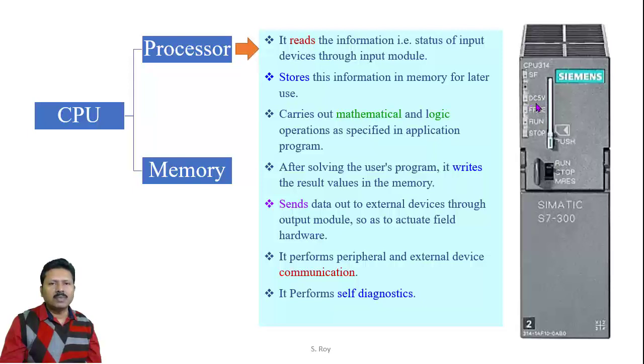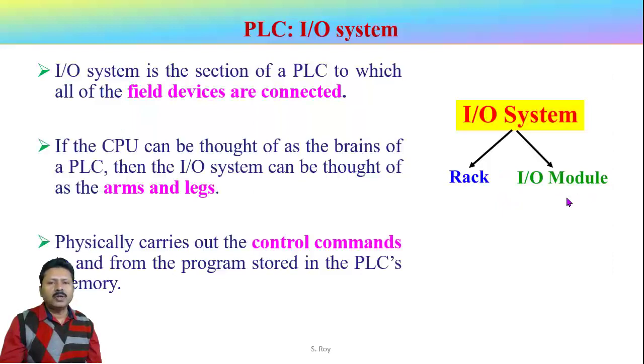Here is one example of a CPU — the Siemens S7-300. We can see a DC 5V indicator LED which indicates that there is a power supply. FRCE gives indication when inputs might be forced. There is a RUN LED which indicates the PLC is in run mode, and a STOP LED which indicates stop mode. There is also a switch for RUN, STOP, and memory reset — using this switch we can make the PLC run, stop it, or reset all the memory.